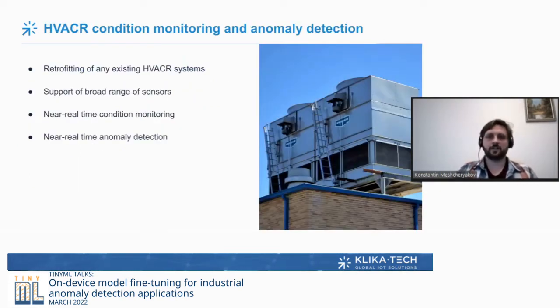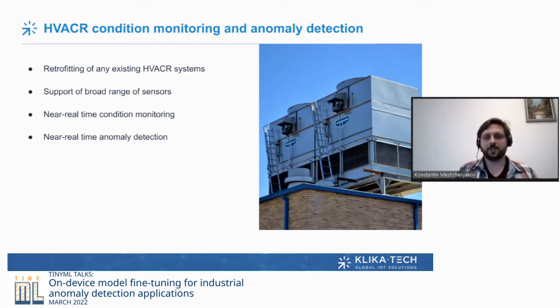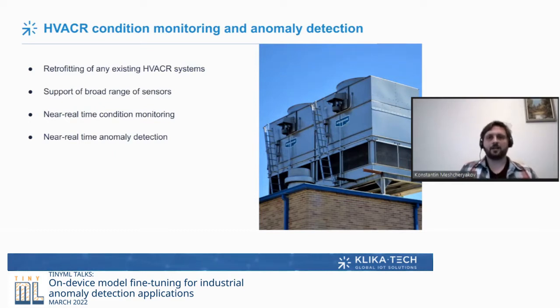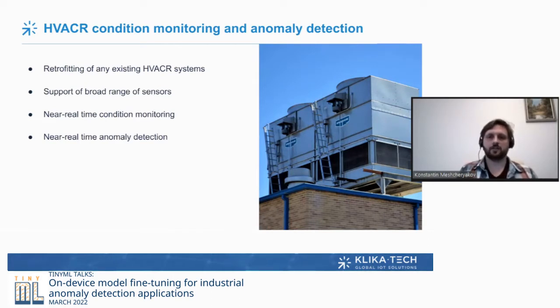For this project, we decided to concentrate on anomaly detection and create infrastructure to collect event data for further implementation of more powerful predictive maintenance models. Together with Infineon, we created complex hardware, embedded software, and cloud software that can find anomalies in HVACR — Heating, Ventilation, Air Conditioning, and Refrigeration units — that can be installed on large industrial buildings but also on consumer air conditioner units. The main task was to retrofit any existing system without replacing it.